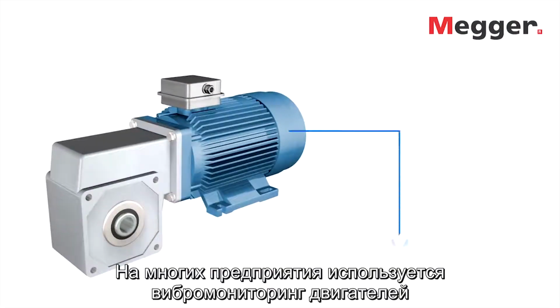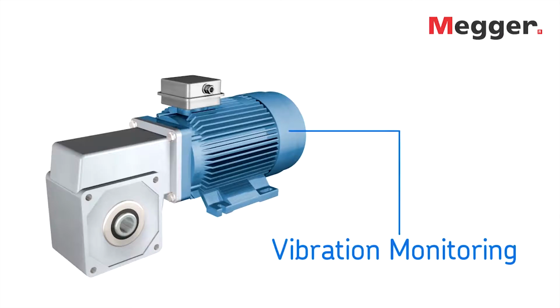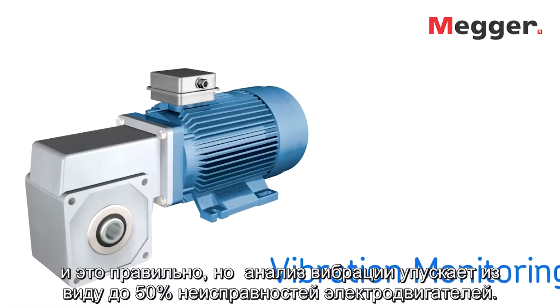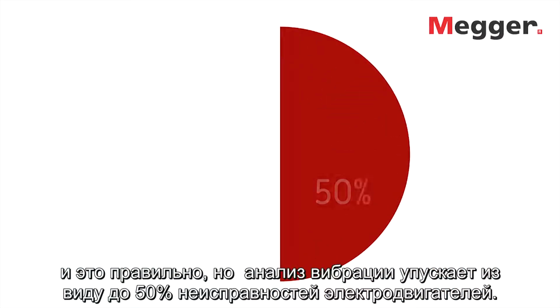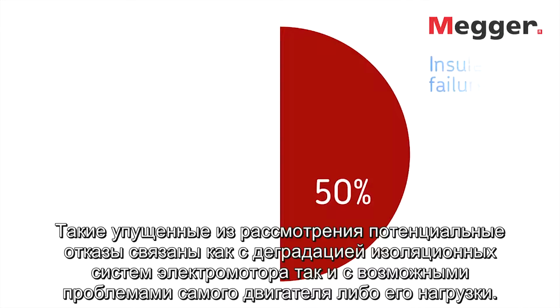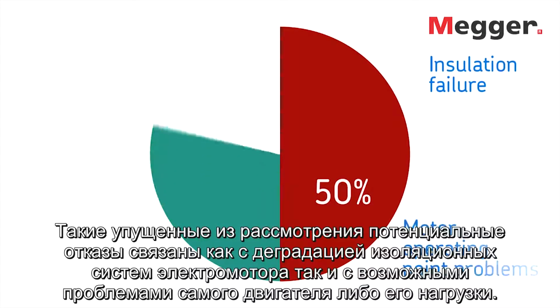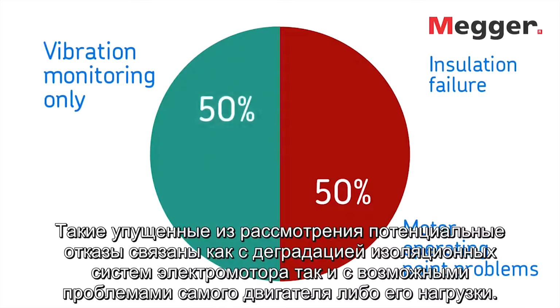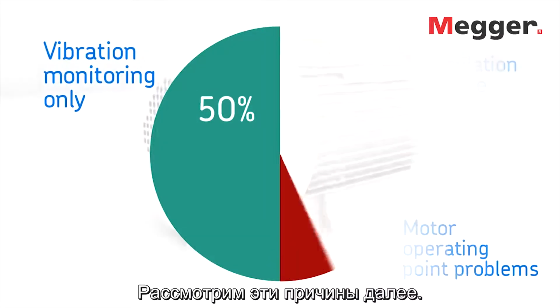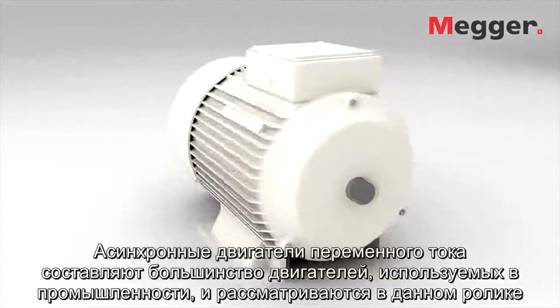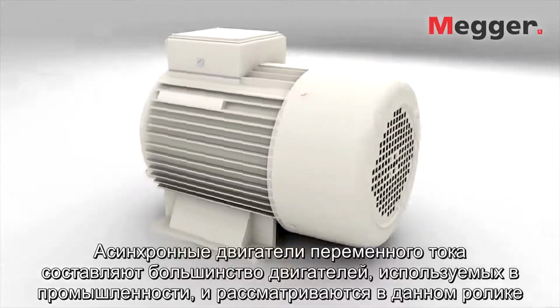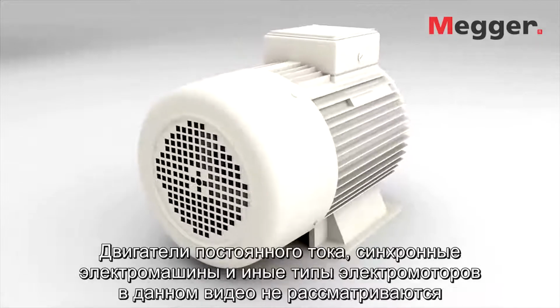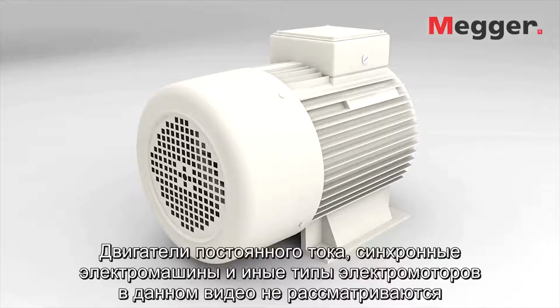Many sites use vibration monitoring on their motors. This is good, but vibration monitoring misses up to 50% of motor failures. These failures are due to insulation failure and motor operating point problems. Let's look at each. AC induction motors make up the majority of industrial electric motors and are covered here. DC, synchronous, and other motor types will not be covered in this video.